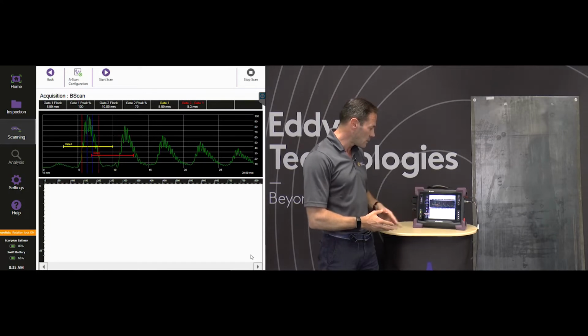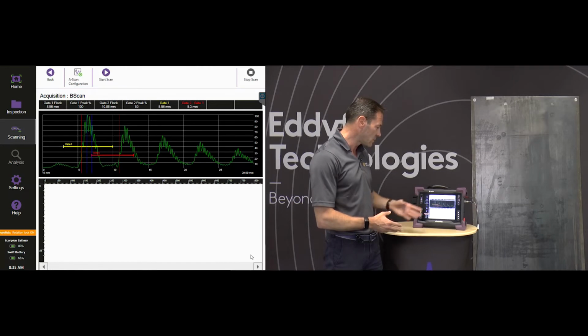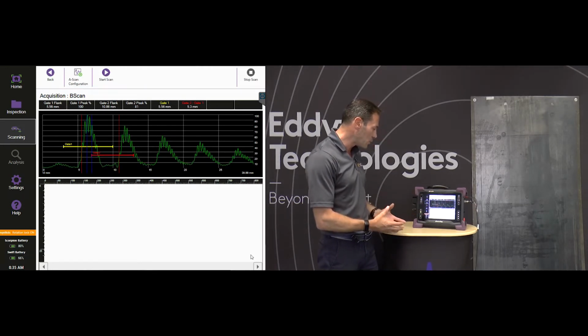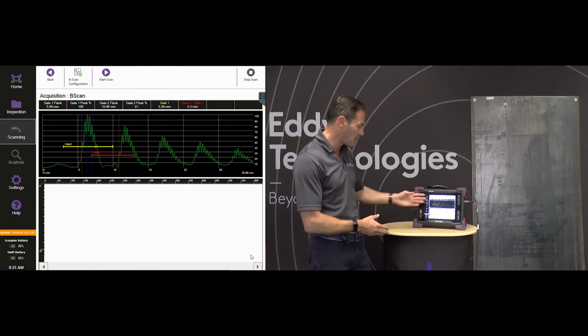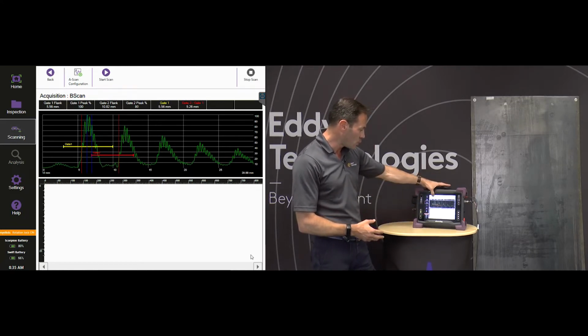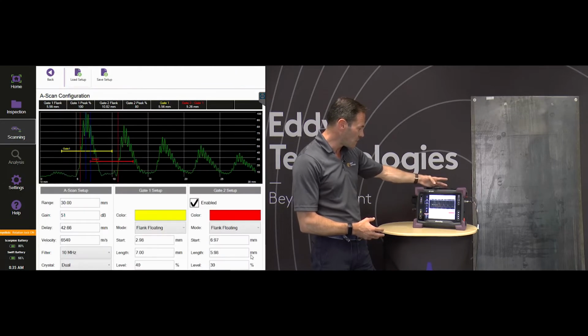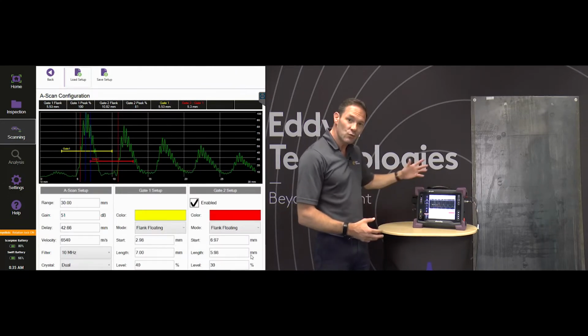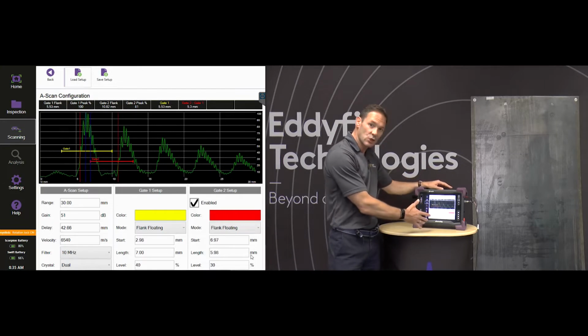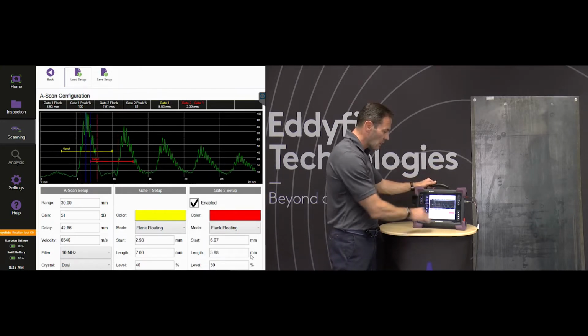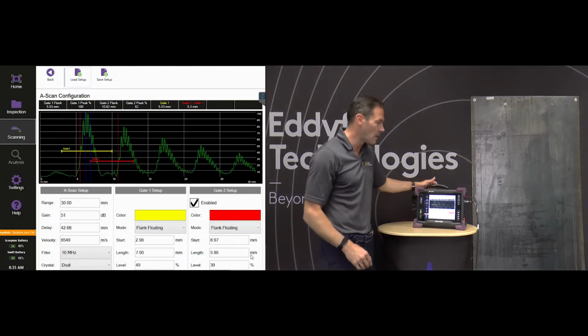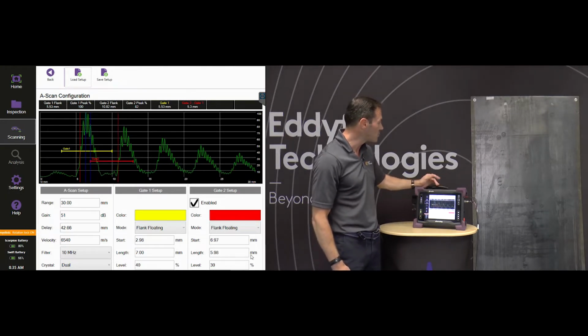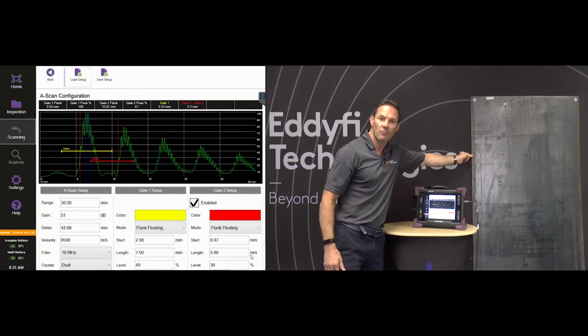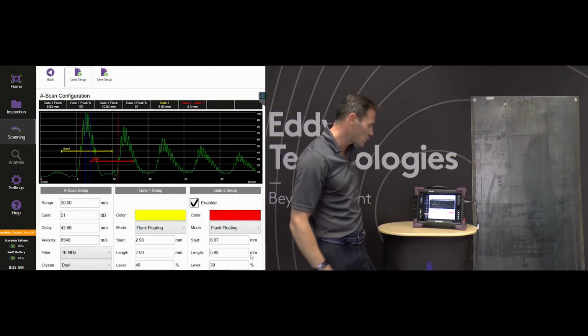On top of the A-scan you will see the most used values for the system, so you can see the different options for the gauge, like the thickness, the amplitude height of the different envelopes. And what you can do then is change your UT configuration settings. With the UT configuration you have the option to set the range. It's currently set to 30 millimeters. We see 4 to 5 envelopes, reflections, back walls on a 5.3 millimeter plate, which is quite nice.